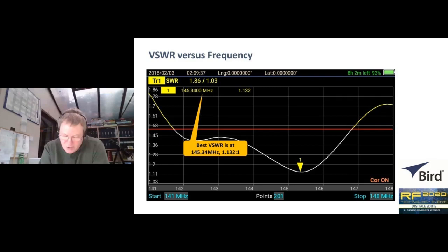Again, our touchscreen interface allows us to provide pull-down menus for limit lines and markers. In this example, the software has automatically translated our previous limit line of 14 decibels return loss into a limit line representing the same voltage standing wave ratio, which is 1.5:1. You can see that on the left-hand side of the screen. The various figures there represent VSWR.